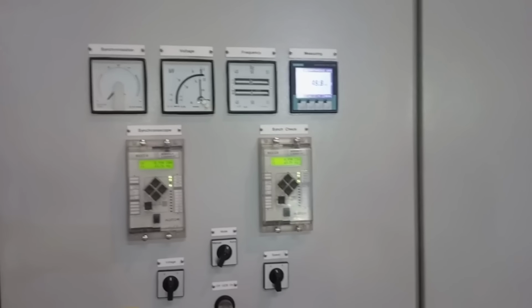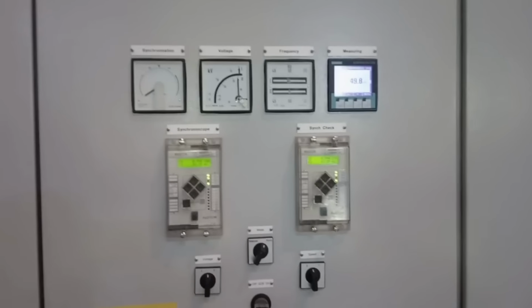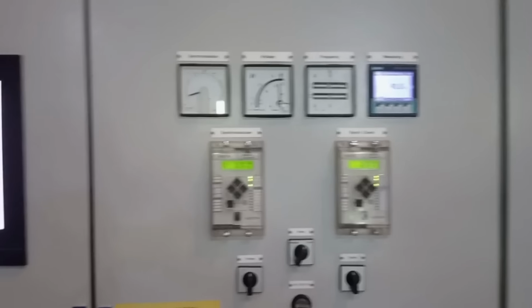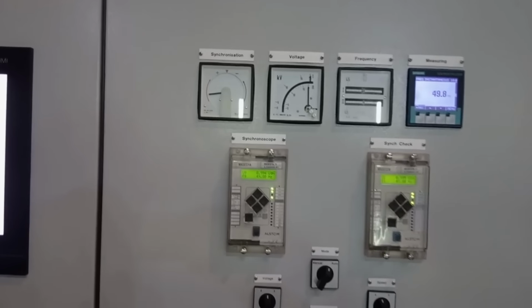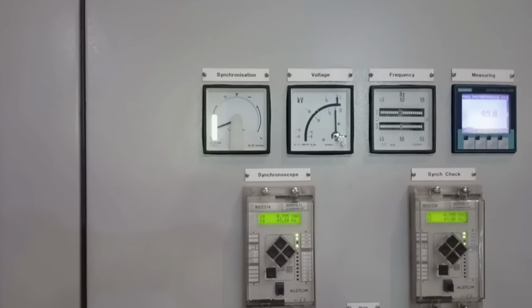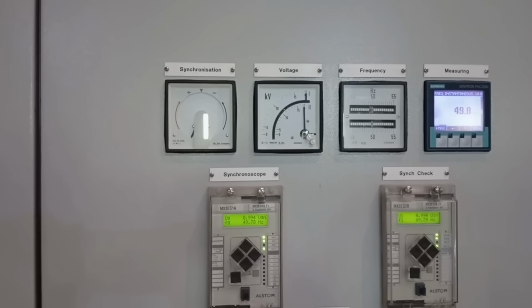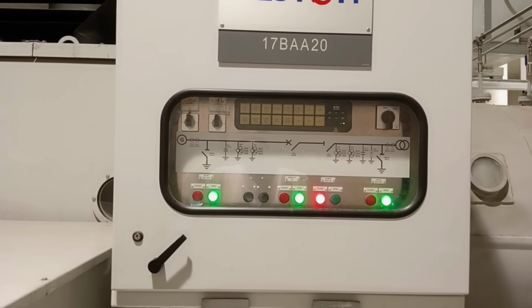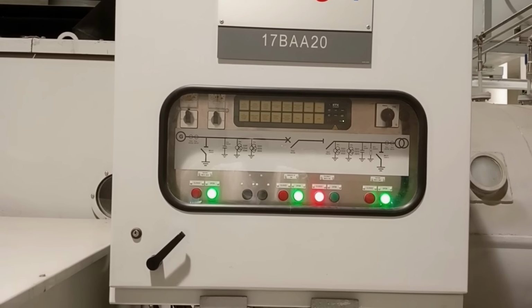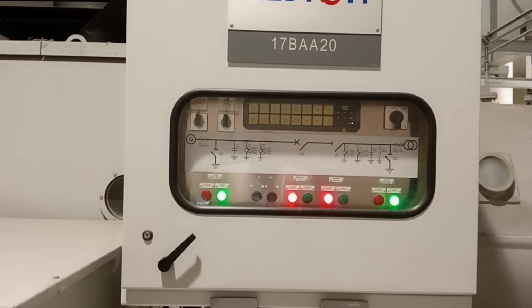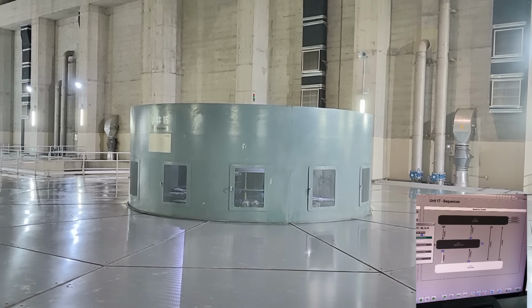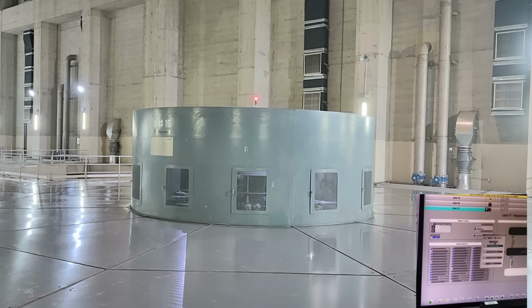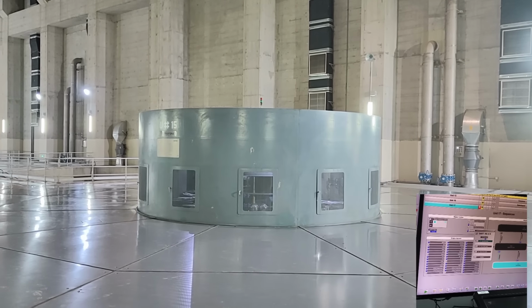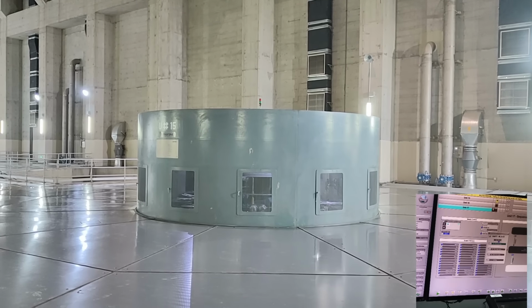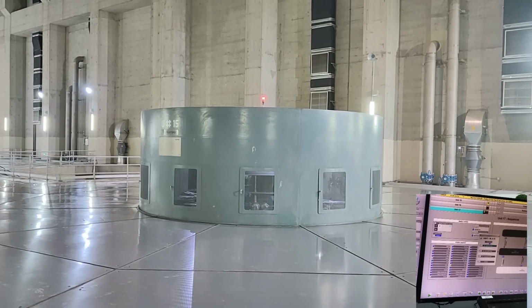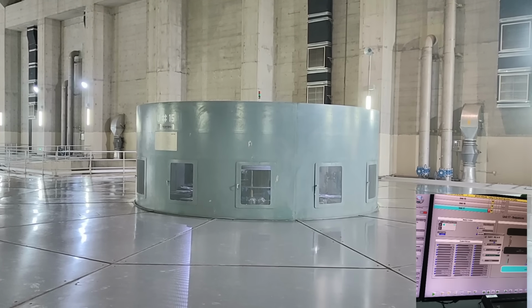So here on the screen you can see the frequency, voltage, and phase angles being aligned, and then when these parameters are aligned, the generator breaker, or GCB, closes at the exact instant. This machine stops being only a rotating mechanical system and becomes a 470 megawatt power producer connected directly to the electrical grid. All of this happens through heavily automated SCADA controlled logic.